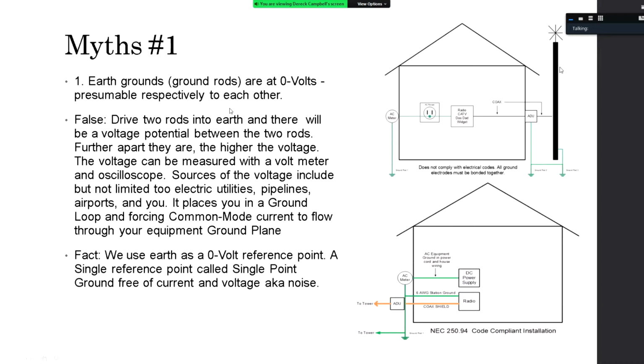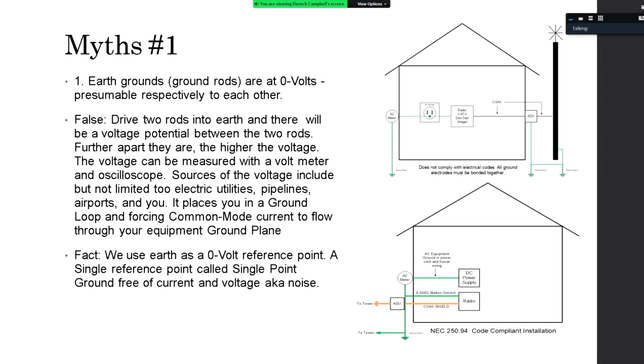Come from airports and pipelines and such, other companies that use cathodic protection systems on the grounding systems. Fact is, we do use the Earth as a zero reference point. We can bond as many rods as we want together, but we only bond to that Earth electrode one time. It's our single point reference point. And if we do that, that ground will be free of current, voltage, and noise.